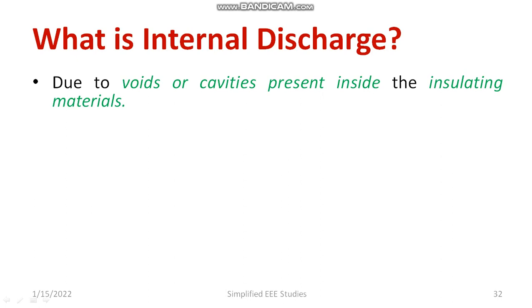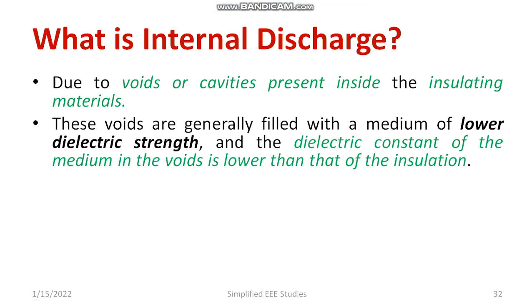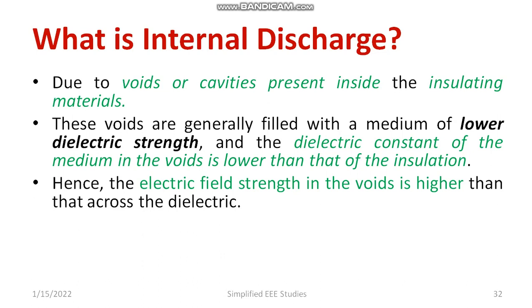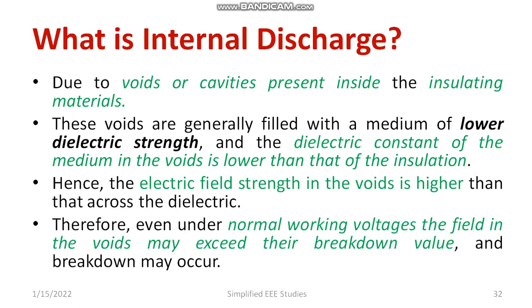First, you need to understand what internal discharge is. Internal discharges happen due to voids or cavities which mainly occur in solid dielectric material. When a void is present inside the solid dielectric material, there is a difference in dielectric constant — the dielectric constant of the void will always be less than that of the solid dielectric material. Because of that, there is a change in electric field strength, which can ultimately exceed the breakdown strength. Such dielectric breakdown is known as internal discharge, and it occurs due to voids, cavities, or cracks inside the insulating material.